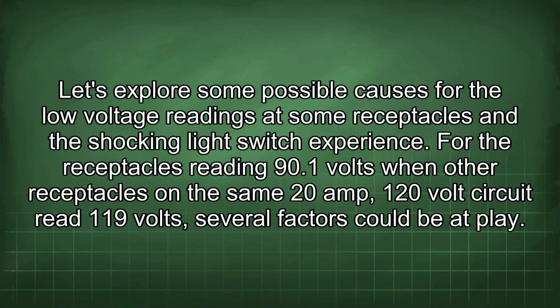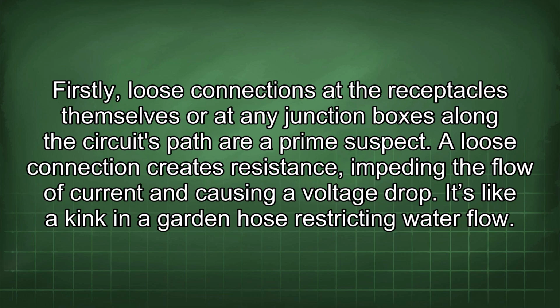Let's explore some possible causes for the low voltage readings at some receptacles and the shocking light switch experience. For the receptacles reading 90.1 volts when other receptacles on the same 20-amp 120 volt circuit read 119 volts, several factors could be at play. Firstly, loose connections at the receptacles themselves or at any junction boxes along the circuit's path are a prime suspect. A loose connection creates resistance, impeding the flow of current and causing a voltage drop. It's like a kink in a garden hose restricting water flow.